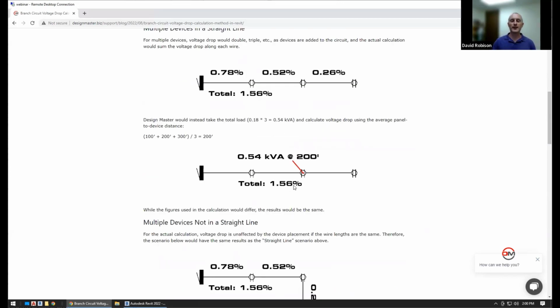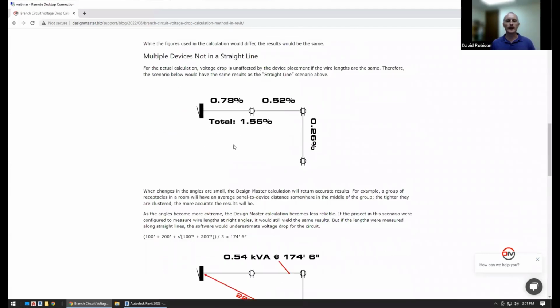For our branch circuits, we take the average distance. So we've got these three in a line. This is 100, 200, 300. You add all those up and they average to 200. And then you do the full load there. And in this case, it actually turns out to be exactly the same. So if they're in a straight line, our calculation exactly matches what you would calculate if you were doing it precisely by hand. All right, so what if we take these devices and we put a bend in them?